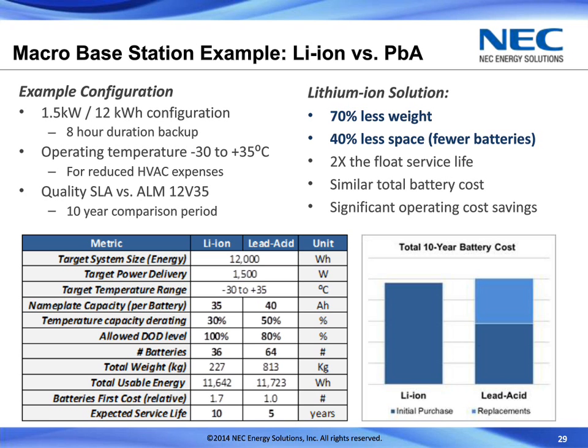So just taking a quick look at the table here, you can see the nameplate capacity is comparable, 35 amp hour for the ALM, 40 amp hour for the lead. But once you get into those deratings that Bob mentioned, for the temperature, for instance, we're derating 30% compared to 50% for the lead. And also, we allow 100% depth of discharge as opposed to 80 for the lead. So once you take those into account, even though the lead has a slightly higher capacity, you still need quite a few more of these lead batteries to get the equivalent configuration of lithium. 64 as compared to the 36 for lithium.